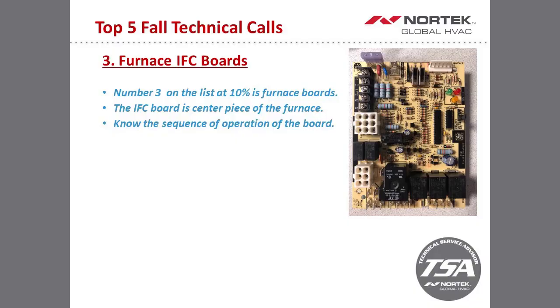So what should happen is when you have a call for W, the first thing that's going to happen is that the inducer is going to kick on. Once it proves pressure switches and that your limit switches are closed, the igniter is going to start to fire up. Once that happens and the igniter warms up, you'll then have voltage to your gas valve. And then once the gas valve releases the gas, the furnace then should light. So as long as you know that in the sequence of operation, depending on how the troubleshooting call goes for you guys in the field, that will help you out.